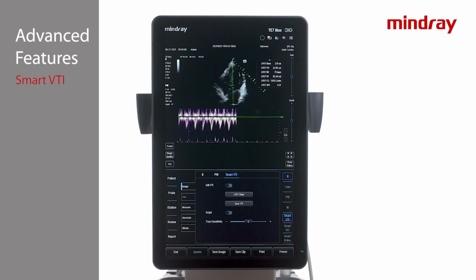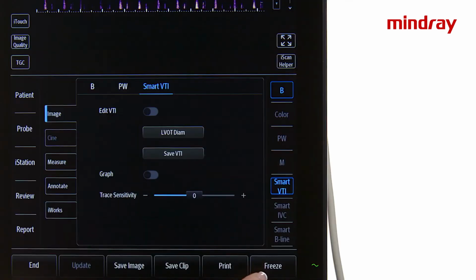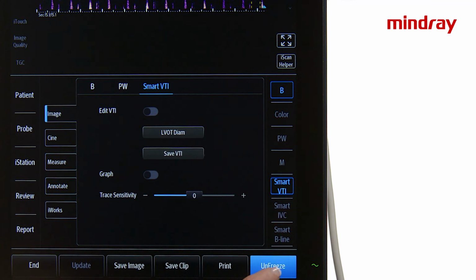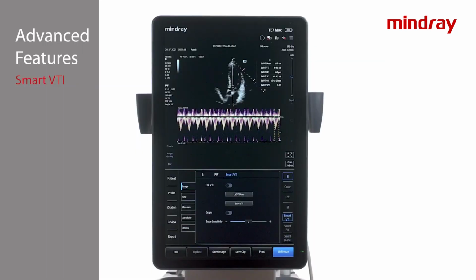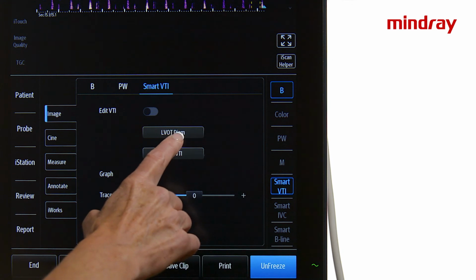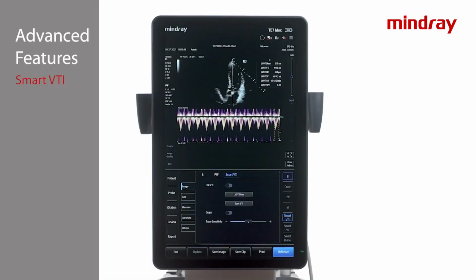The system will begin auto-tracing the Doppler envelopes and calculating VTI, SV, and CO data. Press freeze to stop the Doppler acquisition and the system will analyze the data. An LVOT diameter is necessary to calculate stroke volume and cardiac output. So if it was not manually measured earlier, use the LVOT diameter tab to enter a numeric value.